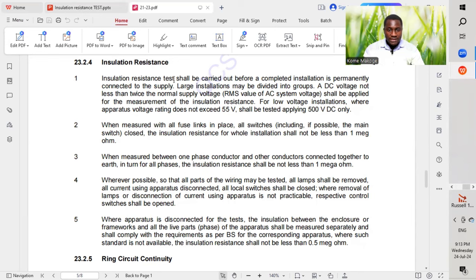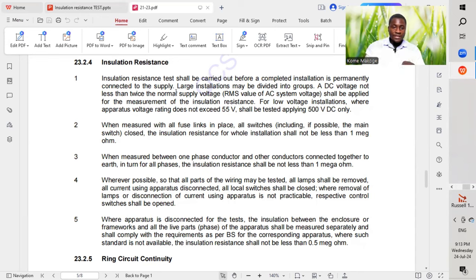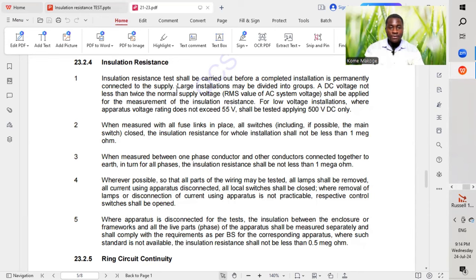Insulation Resistance Tests shall be carried out before a completed installation is permanently connected to the supply. This tells us that we have to carry out this test while the installation is dead — we do not have any electrical power supply to the electrical panel box that will be under test.